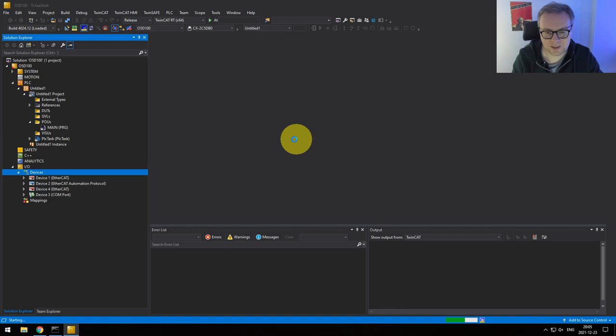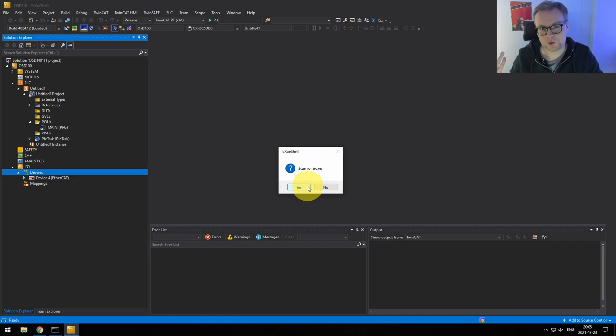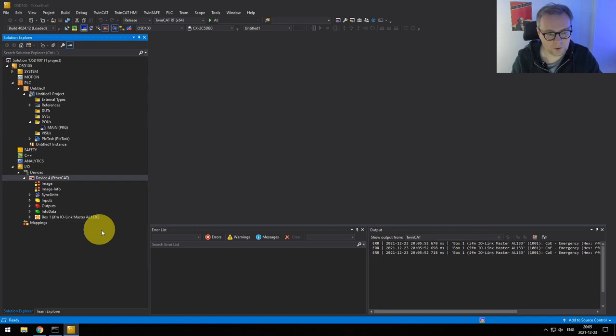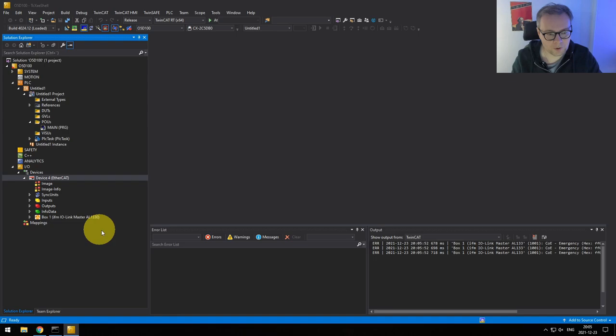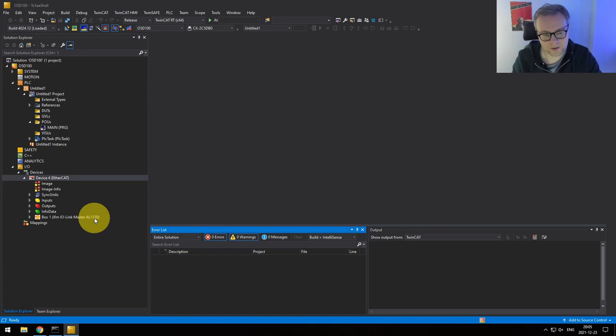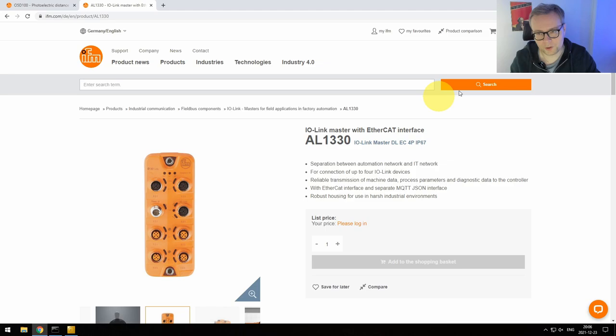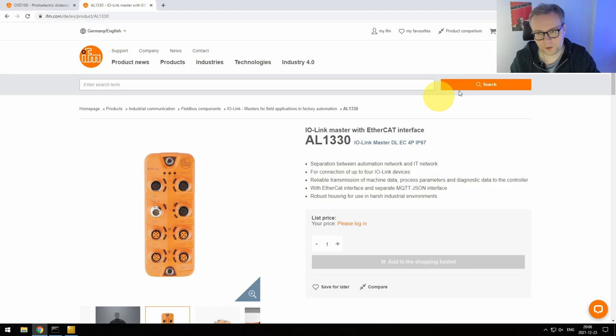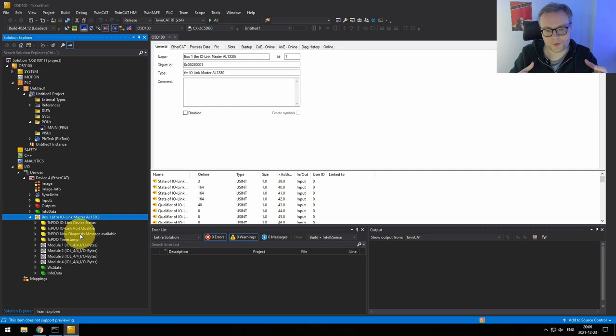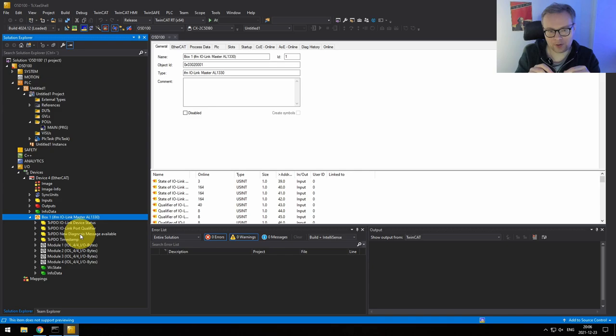Select the network adapter going out from the PLC and click OK. Scan for boxes — basically asking 'do you want me to search for EtherCAT slaves?' Select Yes. Activate free run, select Yes. We can see the IFM IO-Link master, the AL1330, has been detected. We can see its default inputs and state for the EtherCAT slave. Now we need to tell the device that we have a specific sensor connected to port number one, since the IO-Link slave — the distance sensor — is connected to the first port of the IO-Link master. To do that we go to Slots to configure the different channels.